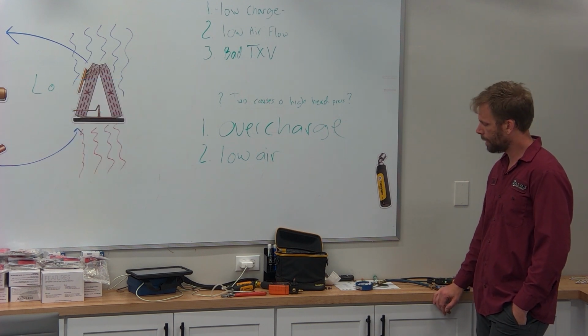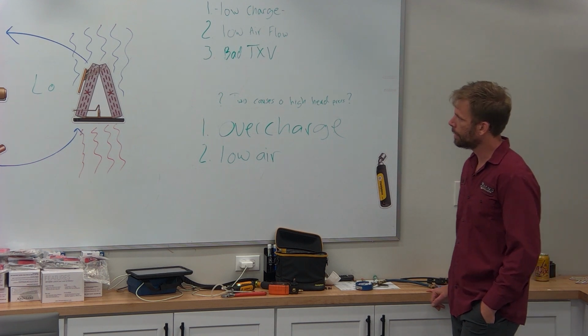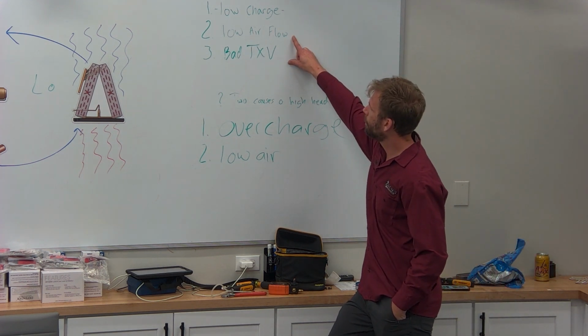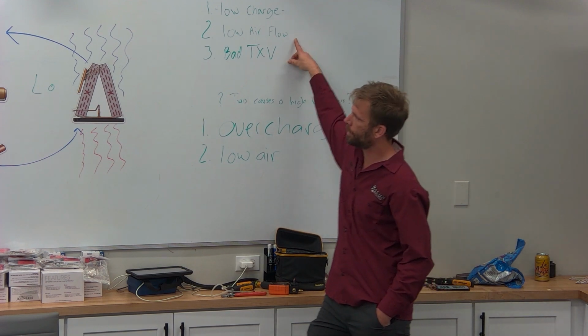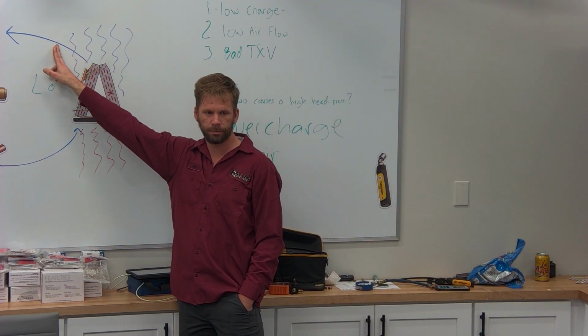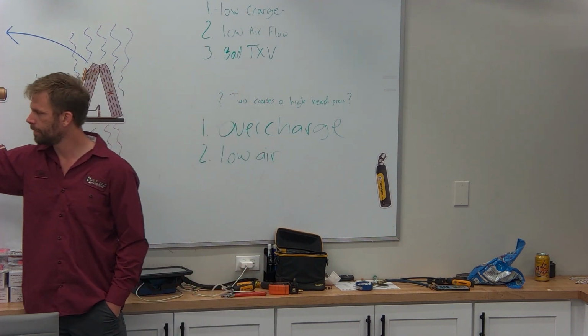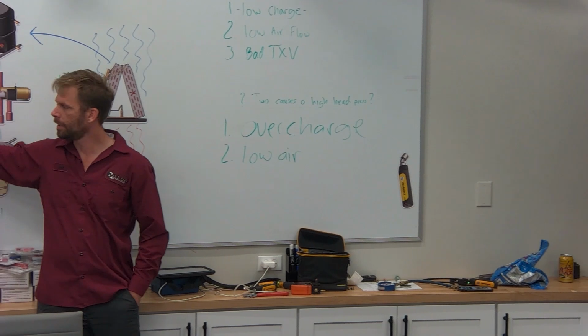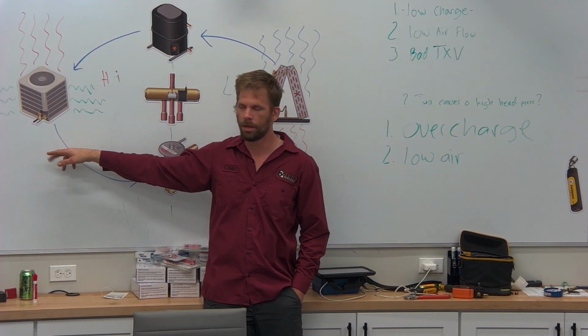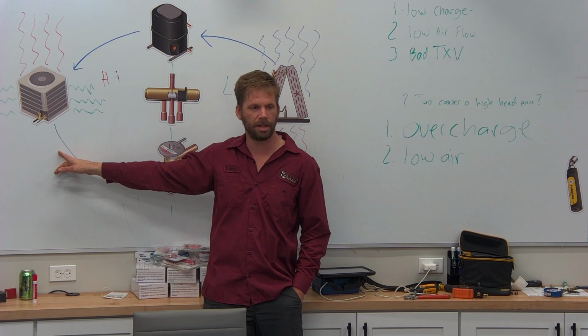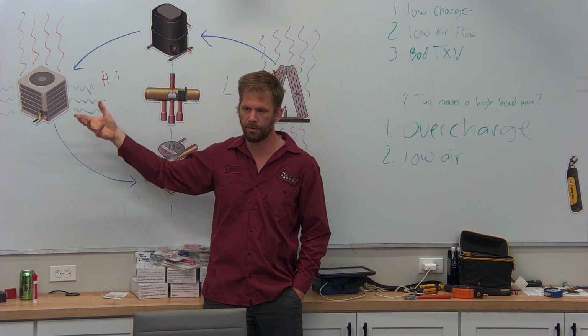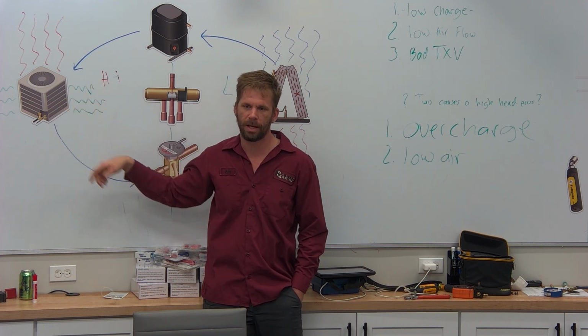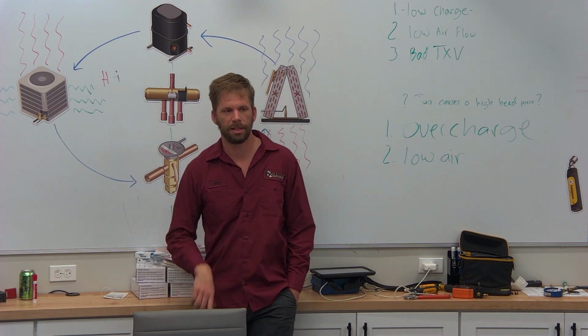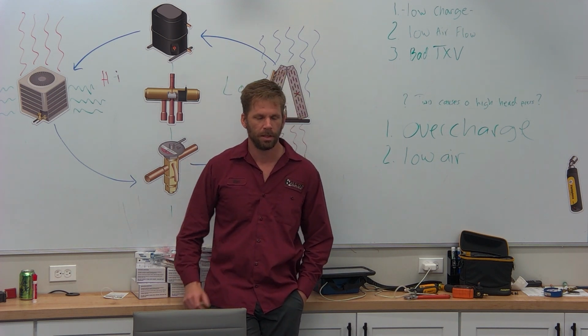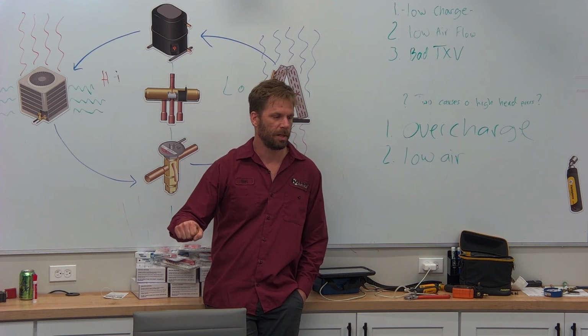And a much easier way of actually doing this would be the same test with low airflow. Over here, if our suction line's cold, we have low airflow. Well, if our liquid line is really hot, we didn't get rid of heat via the air like we were supposed to. So if our liquid line is a lot hotter than the outside air, yeah, somehow that heat stayed trapped in the refrigerant. We didn't get rid of it. We don't have enough airflow cooling that refrigerant down. So it's one of the easiest things to do to see if your coil is efficient is take a temperature. You can just grab the line.